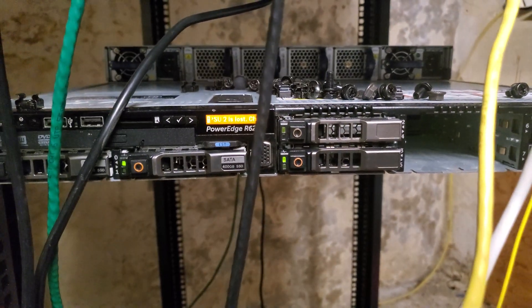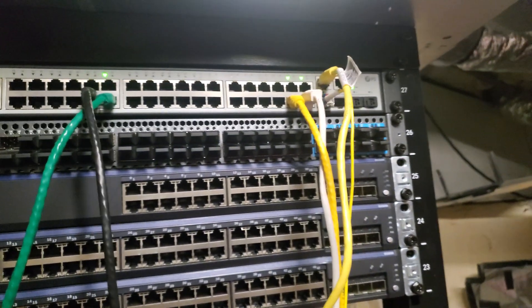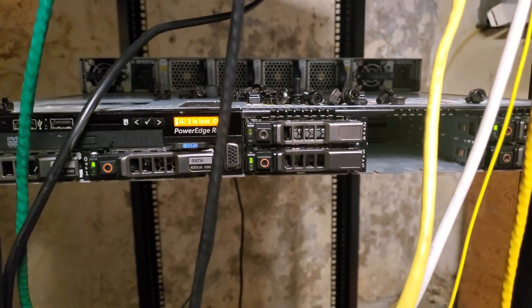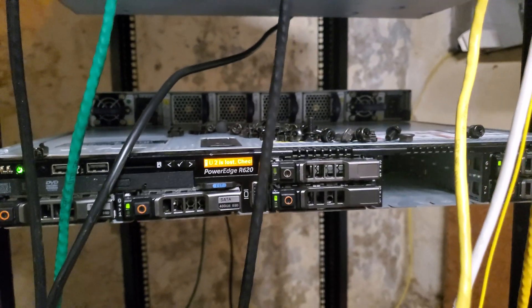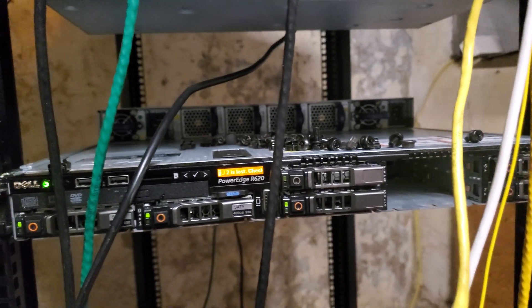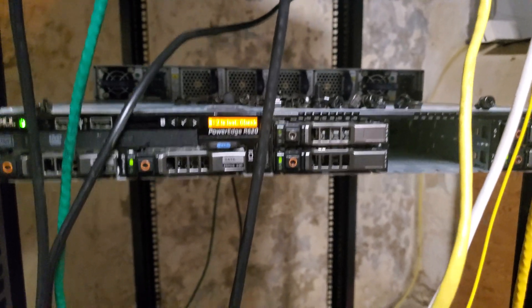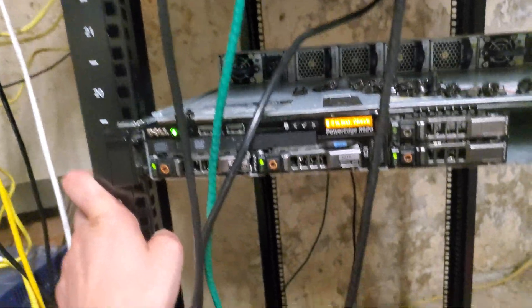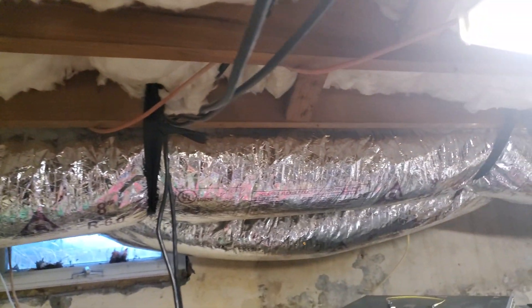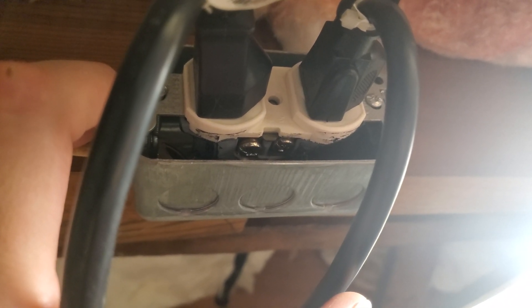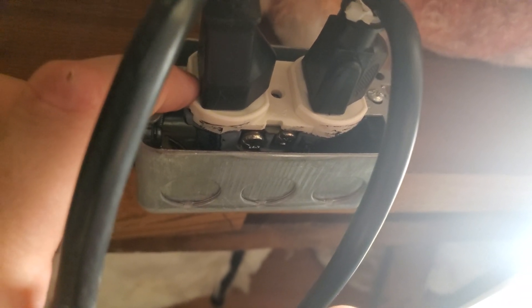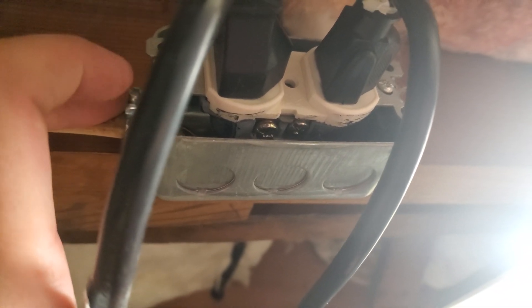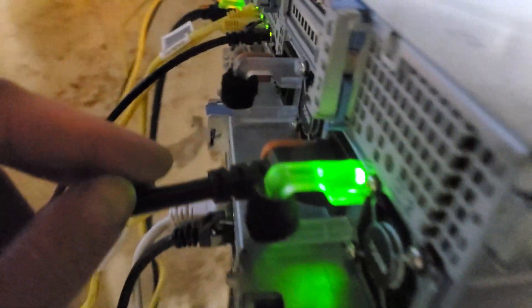I'm gonna come through and put all this cabling, it'll be better. But the power, we're running all the equipment at 240 on the primary power supply. Pretty much how I do that is, I'll show you. The easiest way to pull that off, this is a regular receptacle like you would see, a 20 amp receptacle and it's 120 volts typically. All you do is replace the neutral on the other side and then now these are 240. There's nothing wrong with it, the wiring is all the same.